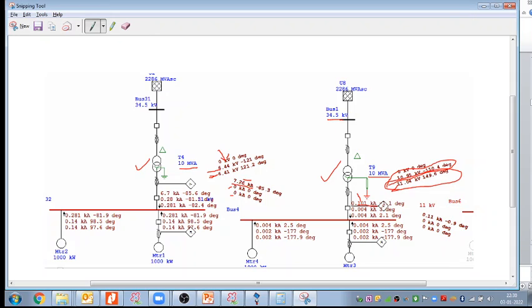We can very well sense it with the help of the CT and the relay. And as we know, in an extra high voltage substation, what is my circuit breaker opening time? What is my breaker opening time for the extra high voltage substation? Breaker opening time. I hope you know the breaker opening time. For 33 kilovolt it is always NGR, not always, but I'll come to NGR, when NGR, when not NGR, that we also need to discuss for the 33 kilovolt system. But what is the breaker opening time for the extra high voltage substation? Breaker opening time, not the breaker withstand time.